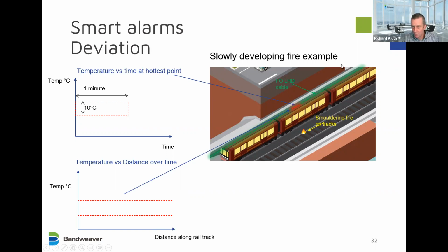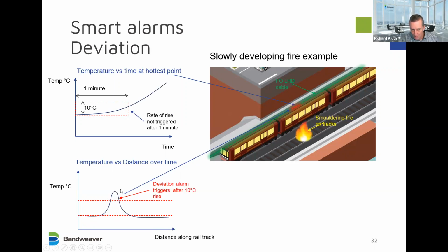So if we take the example here, we've got a rail track, and we have a small fire developing here. In this top graph we'll look at how the temperature develops against time at this point, and this other graph will show the whole distance, and we'll see how this small fire develops. You can see the fire starting to grow, and the temperature starting to increase. This is a minute, this is 10 degrees C. After a minute, it hasn't triggered. But at the bottom here, we can see this event, and there, it's gone above the 10 degrees C. It took more than a minute, but the deviation alarm will trigger.